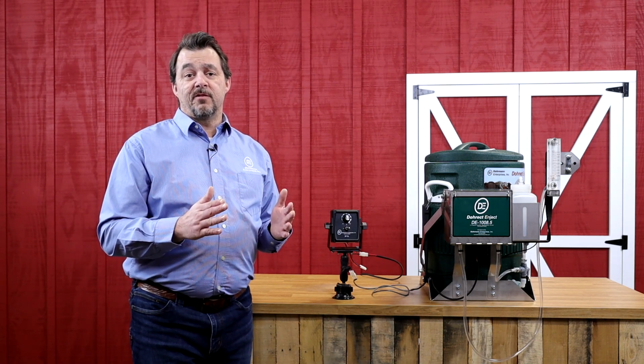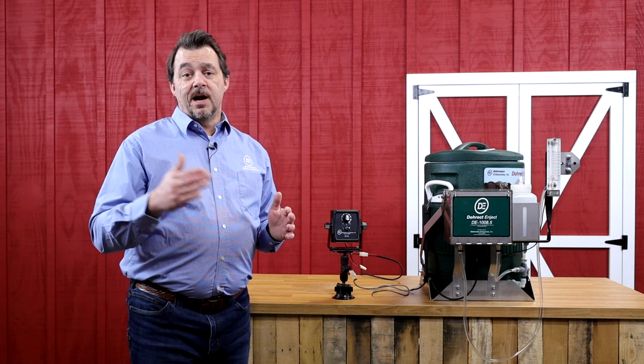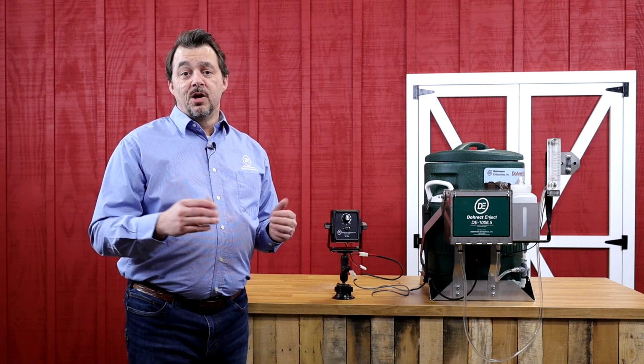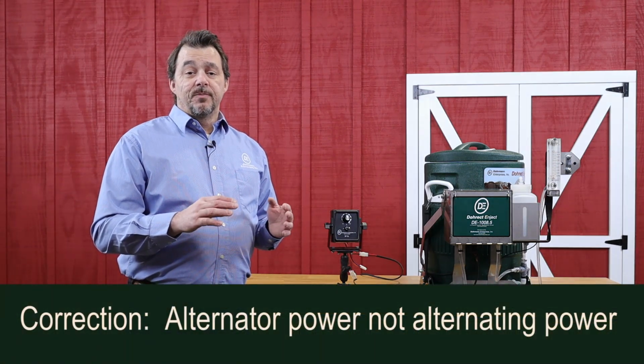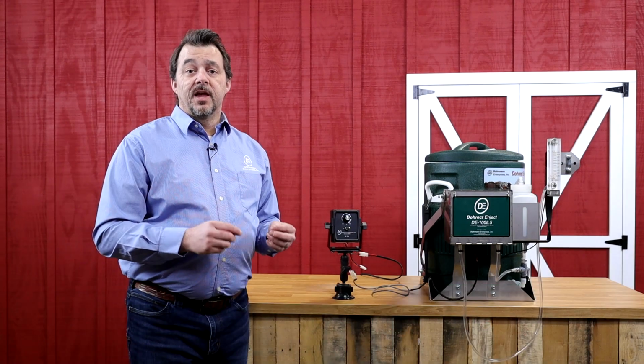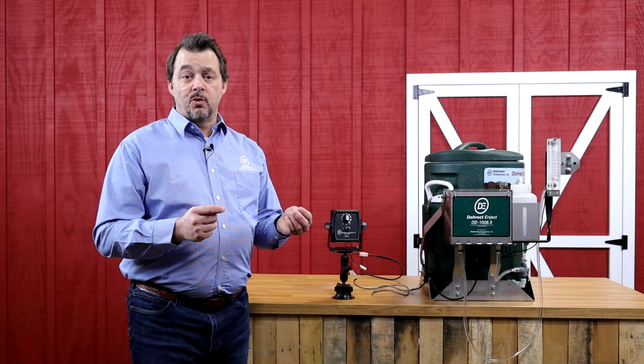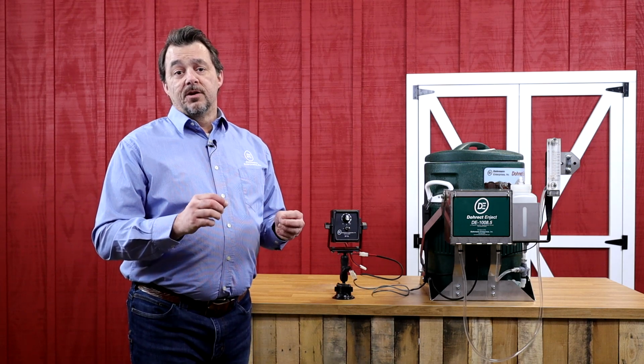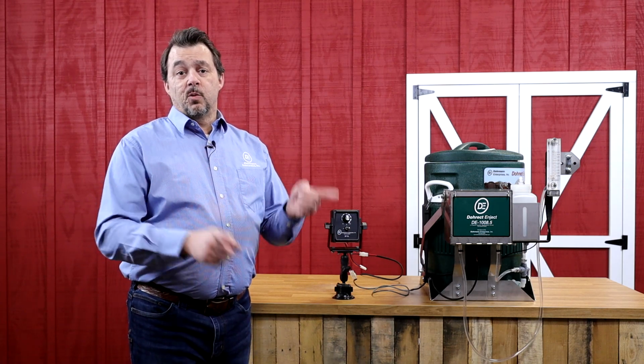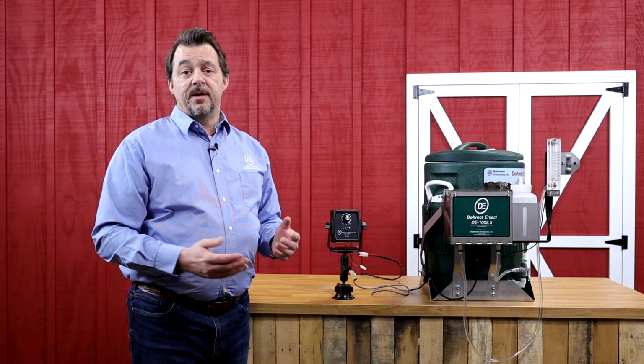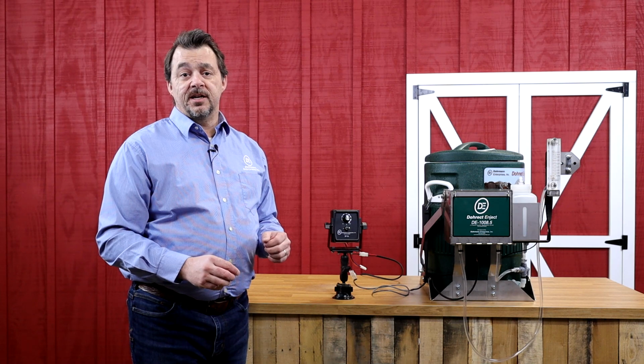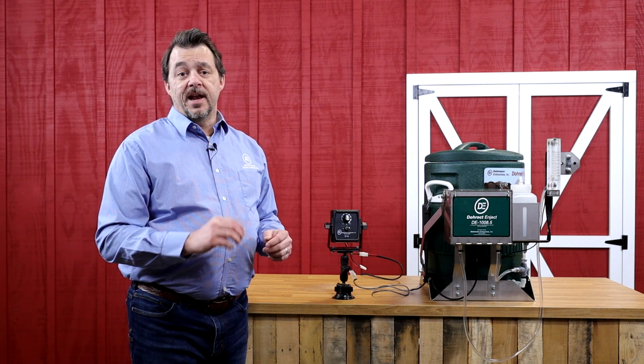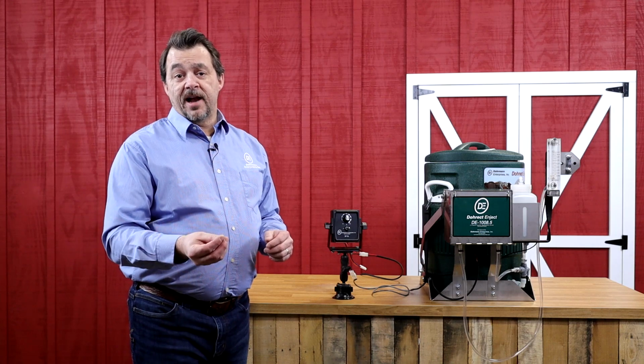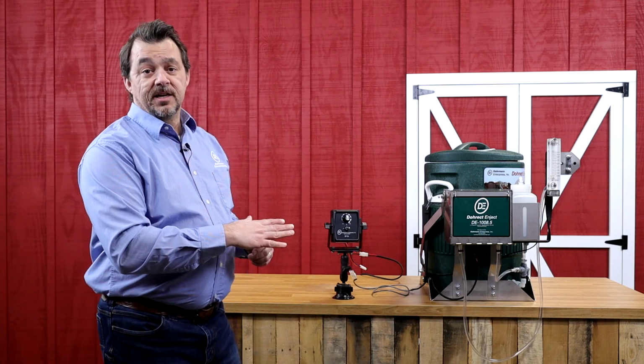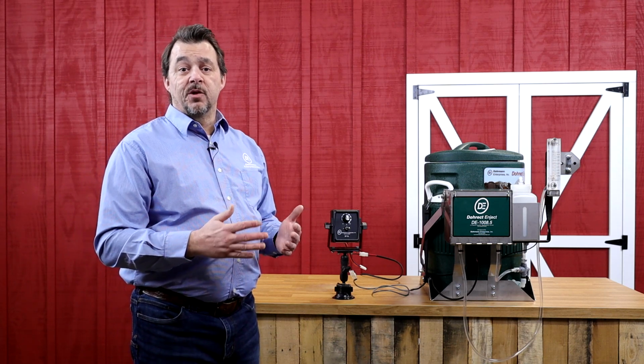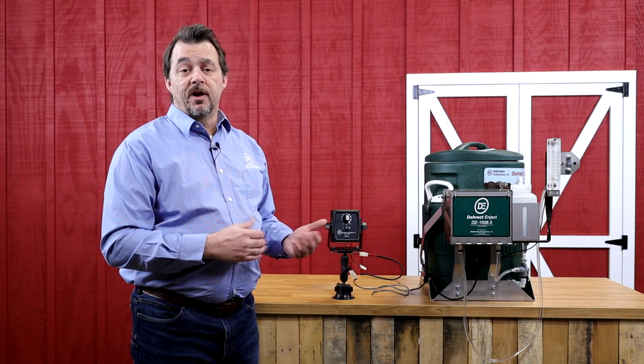Two, we need to make sure that it's a 12-volt system. Essentially we need to be between 8, 9, 10 volts on the low side up to about 15 on the high side, depending on whether we're dealing with alternator power or not. And then we also need to make sure that it's wired correctly. What I mean by that is we need to make sure that the power and the ground wires are both connected to the appropriate terminals in the power supply. If those are wired backwards, that is what's called reverse polarity. Our controller has reverse polarity protection in it, which would automatically shut the unit down and not allow power to pass through. That is essentially to protect the unit from going bad, because otherwise, if it were wired improperly, you could fry the controller.